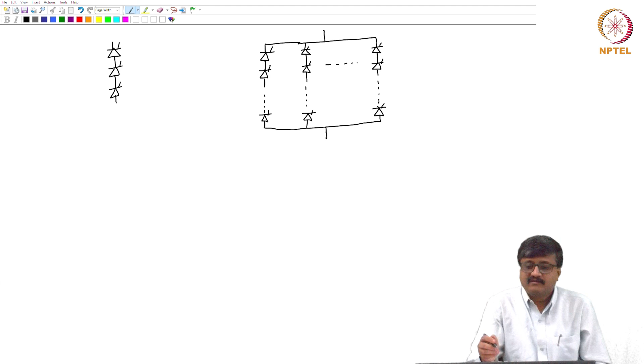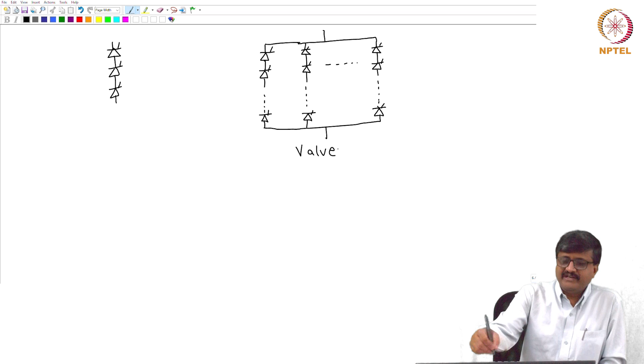But nowadays we do have the current rating, so we no longer need the parallel connections, but we still need the series connection. As I said, if the maximum rating available is 12 kV and I want, say, 500 kV, the minimum number of thyristors that I need to connect is 500 divided by 12. So we still don't have a thyristor device which can withstand the voltage level at transmission, which is hundreds of kV. 500 kV is an example. So right now we don't need parallel connection, we need only series connection, as I have shown here.